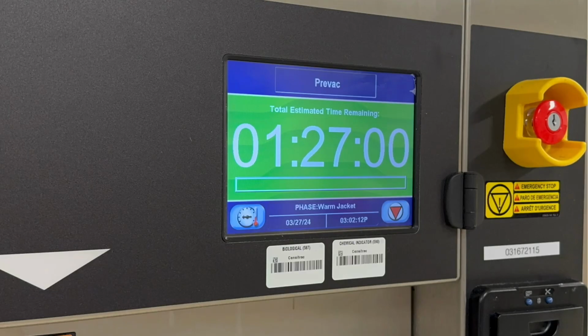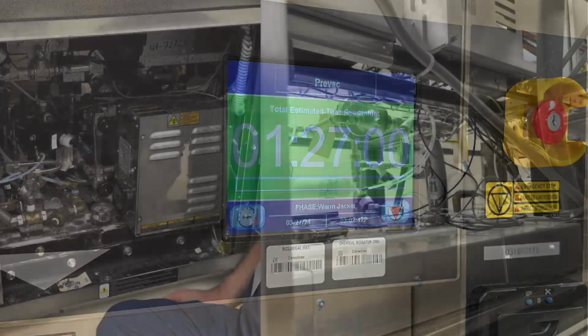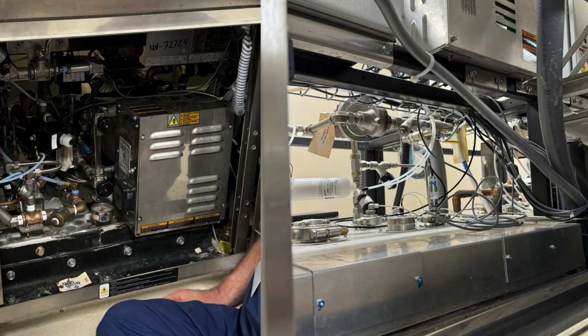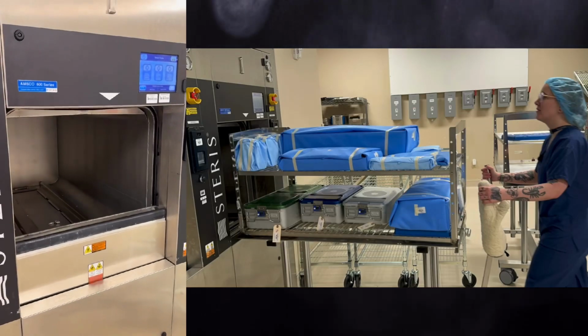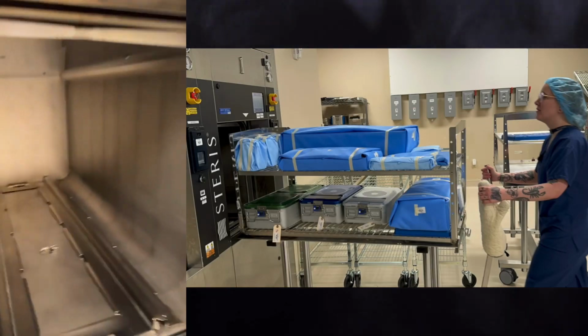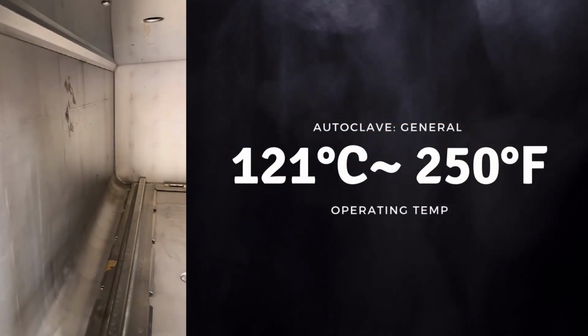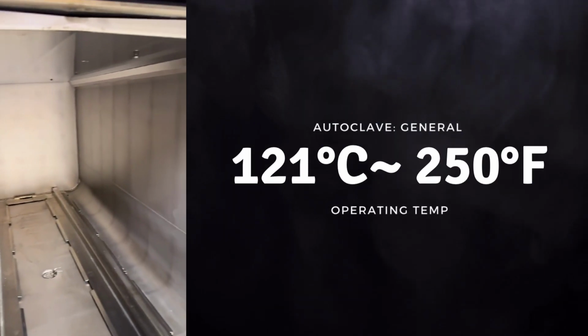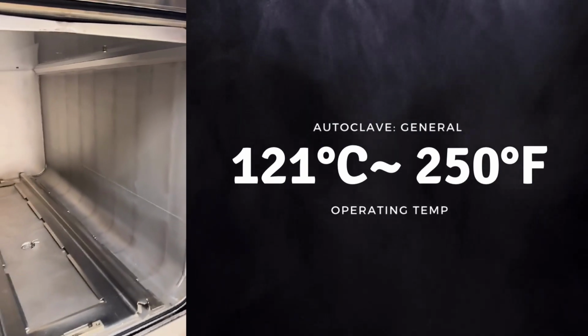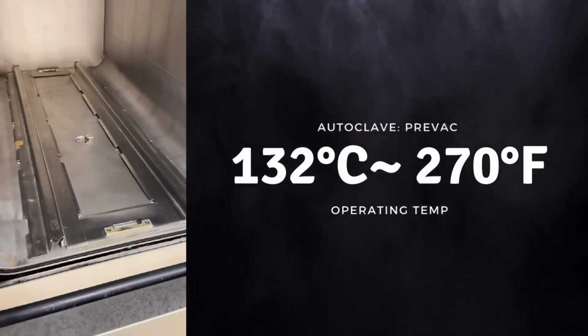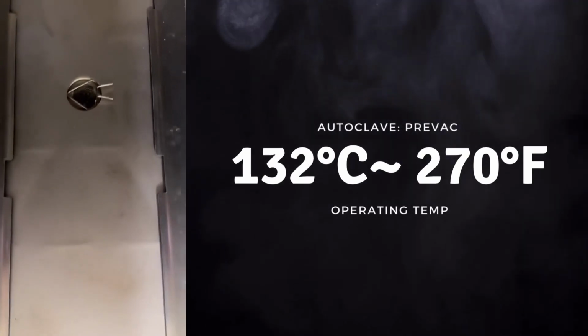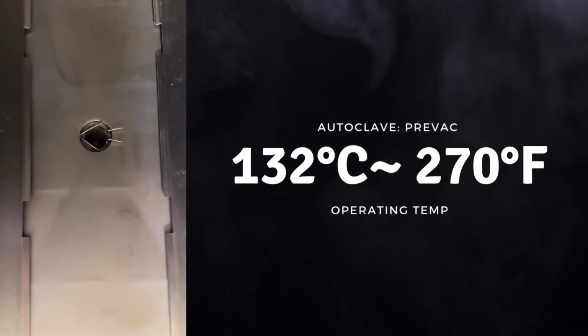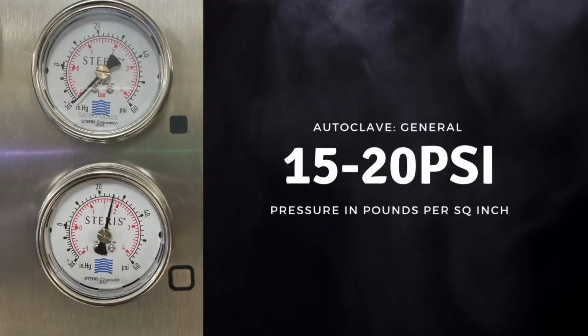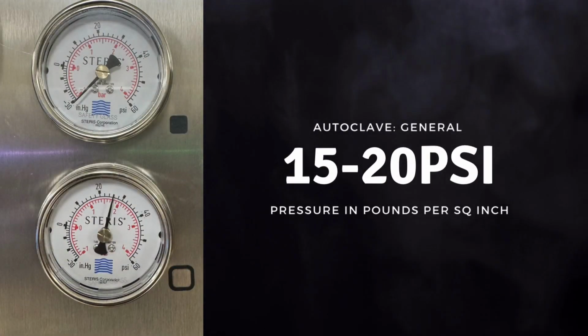However, in my own experience, pre-vac sterilizers are the OR industry standard. The pre-vac cycle uses a high-powered vacuum to rapidly remove all the air out the vent to promote the downflowing steam's ability to adequately penetrate instrument sets. Operating temperatures for autoclaves start at about 121 degrees Celsius, that's about 250 degrees Fahrenheit, and for standard pre-vac cycles, 132 degrees Celsius, which is about 270 degrees Fahrenheit, typically at a pressure of 15 to 20 pounds psi.